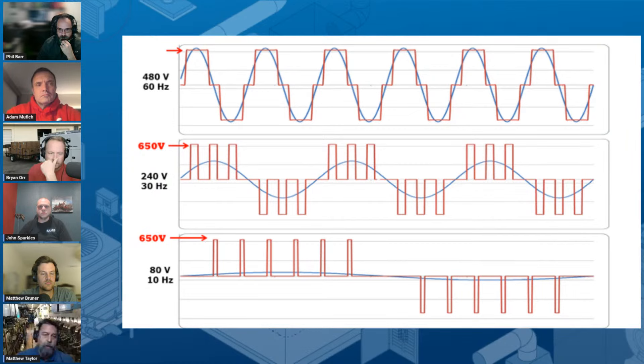This is not highly used — it's not super efficient and definitely not cost effective. If you have three-phase power, you would not do this. But if three-phase power is just not possible and you have a device that can only be three phase, this is the way around that. For all you guys watching thinking 'where would I use that' — in your garage, when you're trying to use a piece of commercial equipment you picked up. I've used it where a donation of a very expensive $25,000 three-phase plastic grinder was given to an organization, so we ran it through a VFD.